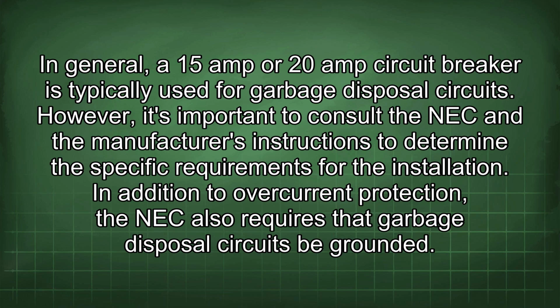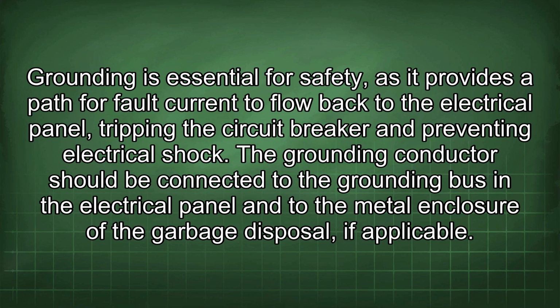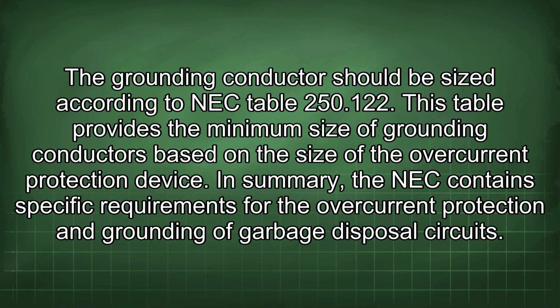In addition to overcurrent protection, the NEC also requires that garbage disposal circuits be grounded. Grounding is essential for safety as it provides a path for fault current to flow back to the electrical panel, tripping the circuit breaker and preventing electrical shock. The grounding conductor should be connected to the grounding bus in the electrical panel and to the metal enclosure of the garbage disposal, if applicable. The grounding conductor should be sized according to NEC Table 250.122. This table provides the minimum size of grounding conductors based on the size of the overcurrent protection device.